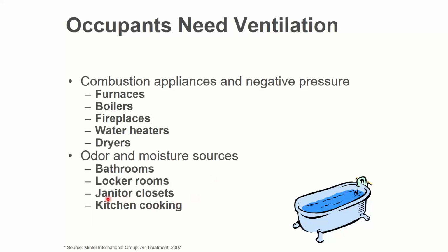If I have places storing and using chemicals, like a janitor closet, directly exhaust it. If it's a commercial building with a kitchen, there should definitely be exhaust sources there—even if it's a small building with just a kitchenette and no oven or stove. I might still want an exhaust fan because people are cooking stuff in the microwave, and there can be odors from whatever odd-smelling food they like and you don't. Let's put a small exhaust fan in there just to keep air moving out of the break room. So those are places I want to exhaust on purpose to get rid of air.